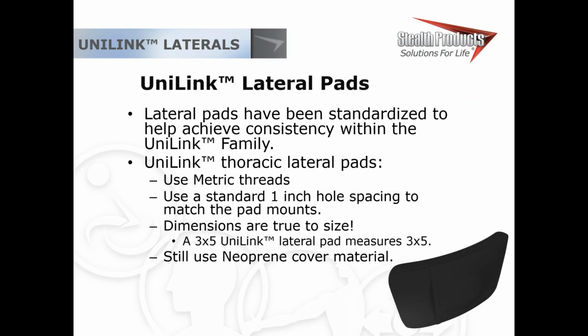So these Unilink lateral pads are going to receive an update as well. Lateral pads are being standardized so that they're consistent with the Unilink family. Our thoracic lateral pads are going to start using metric threads. The hole spacing is going to be standardized.